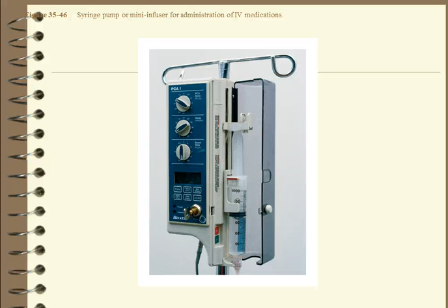Okay. Safety features on these volumetric pumps. They have sensors that detect air in the tubing. They have sensors that detect back pressure if the line is occluded or clamped. Say you walked away and forgot to undo the roller clamp after you started the infusion, or the IV is infiltrated and has backup.